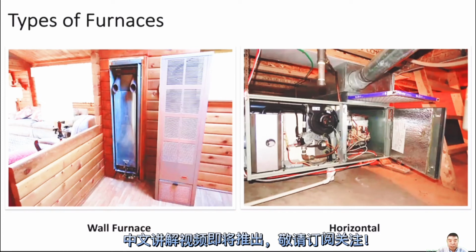If you change the install direction, like downflow or horizontal, just like I said before, you need to read the manual and check how to change the direction of the inducer motor, and some things like the drain pipe. Maybe you should change the drain pipe from the top here to here, or from here to here, just to make sure all the condensate water can drain out completely. The horizontal position needs some small adjustment of the various components inside the appliance.